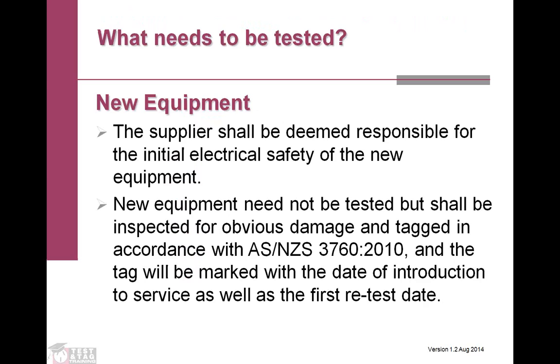So, looking at what equipment needs to be tested. New equipment, we often get asked whether new equipment needs to be tested and tagged. Essentially, new equipment does not need to be tested straight away. It's covered by the manufacturer for the initial period. Where it does need to be tested is normally once it hits its first test cycle. Let's say we've got a manufacturing environment or a really industrial print press area. The test process for that would be 6 monthly. So let's say we install a new press. It doesn't need to be tested straight away before going into service, but when you come around to your next testing cycle within 6 months, it should then be tested. And there is a new to service tag that you can put on those items to say that this item is new to service, and then when the person responsible for your testing and tagging comes back around the workplace, they'll see that it is a new item and they can set it up for the new test sequence.